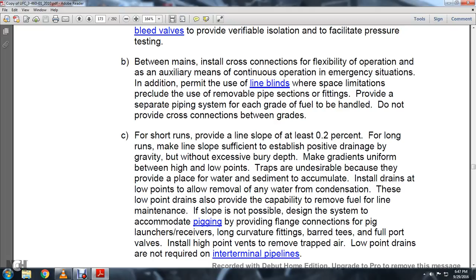Install drains at the low points to allow the removal of any water from condensation. These low point drains also provide the capability to remove fuel for line maintenance. If slope is not possible, design the system to accommodate pigging. Provide flanged connections for pig launchers and receivers, long radius fittings, barred tees, and full port valves. Install high point vents to remove trapped air. Low point drains are not required in inter-terminal pipelines.